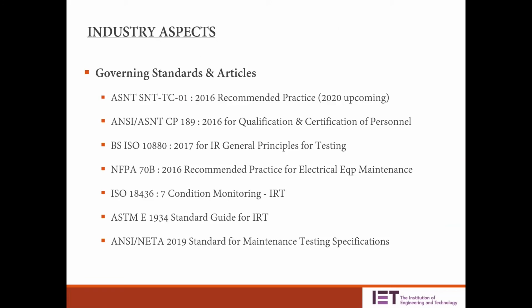There are many governing standards and articles in this area. The main governing article is the American Society of Non-Destructive Testing recommended practice. They have a 2020 upcoming update, and for evaluation we use the ANSI/NETA 2019 standard for maintenance testing specifications. These testing specifications decide how hot is too hot—for example, when you see a conductor hot up to 100 degrees, we know the conductor insulation max is 90 degrees, so we see that it's an exception and should be dealt with through immediate action.